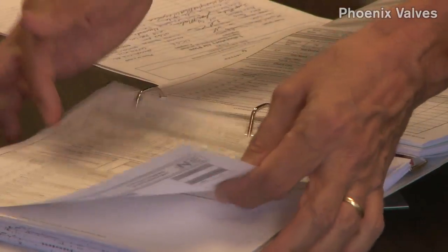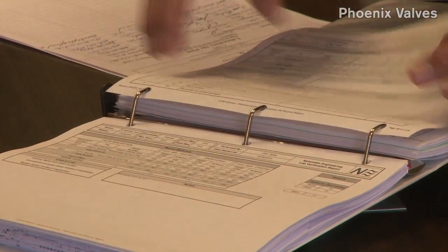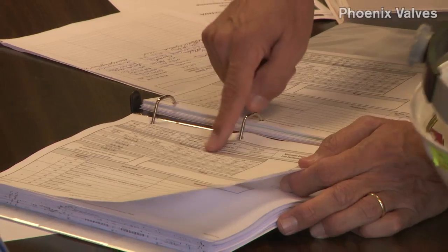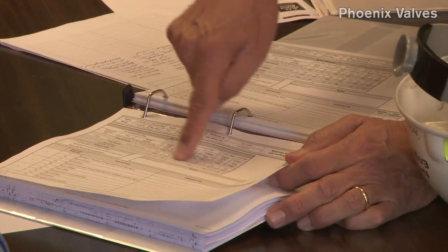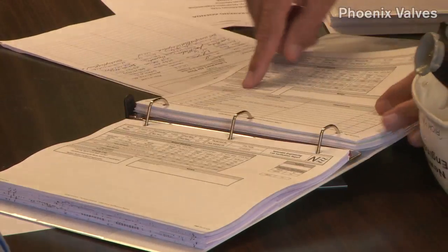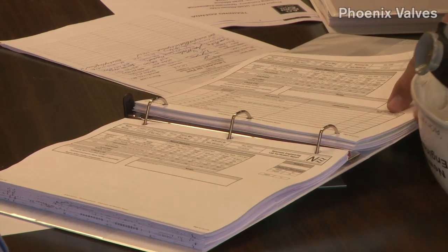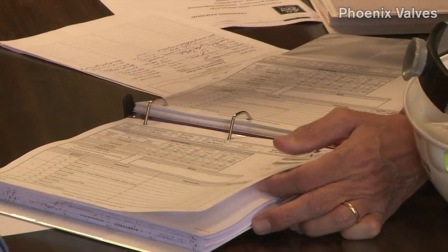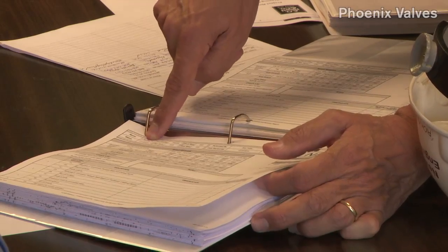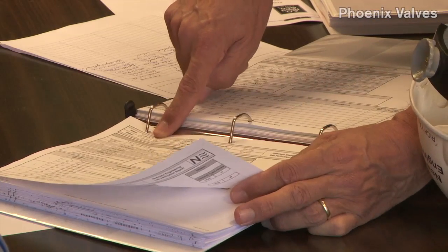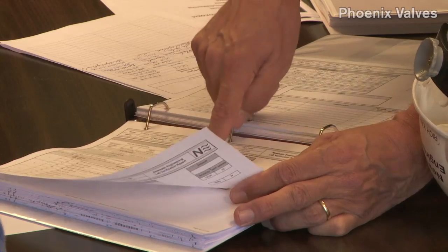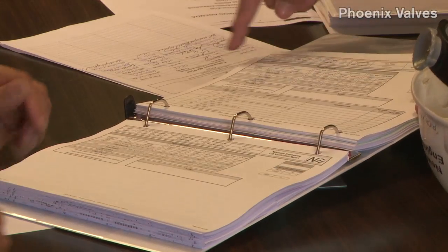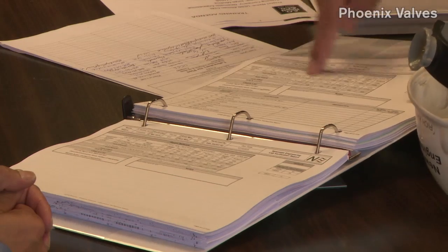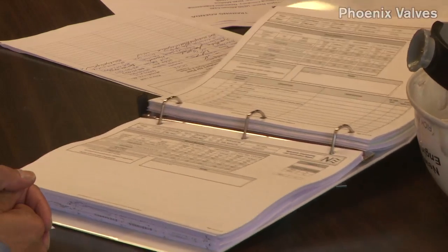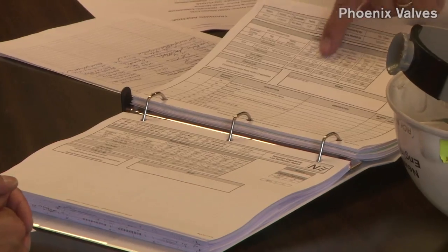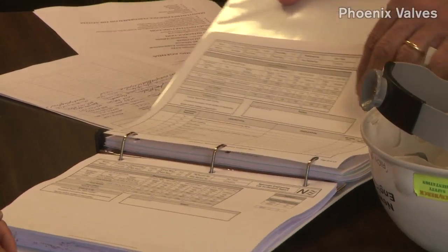These 2 are the same room, but this is in state 2 and this is state 1. So in state 1, the rooms are 95 CFM negative. In state 2, the rooms are 105 CFM positive. That's just showing you. So there are room numbers here. If you're in L3 W334, in switch position 1, the rooms are negative by about 100, and in switch position 2, same room, the room is positive by 100 CFM. And when you see the software numbers filled out, that means Don's been in and checked out the room.